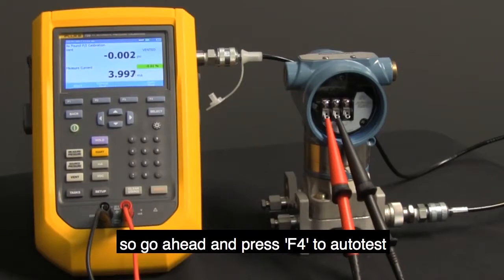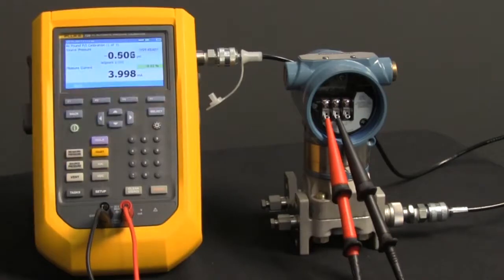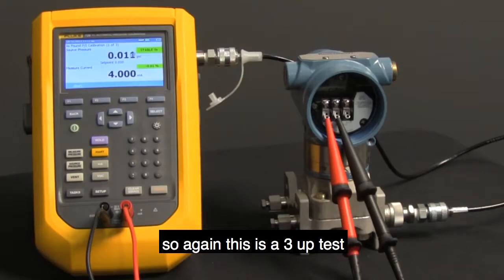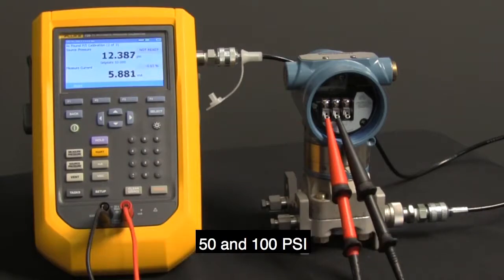So go ahead and press F4 to autotest. And the 729 is going to go to work. So again, this is a three up test. So the Fluke 729 is going to take readings at 0, 50, and 100 psi.